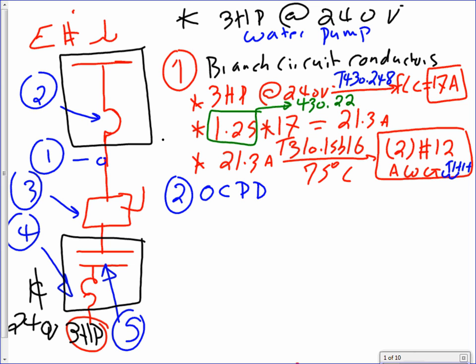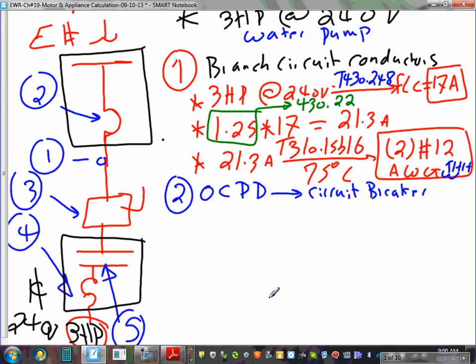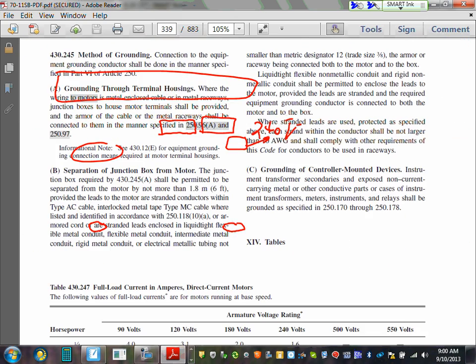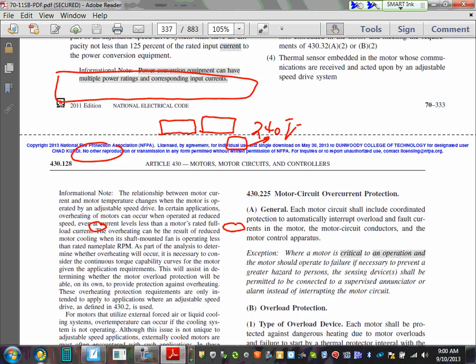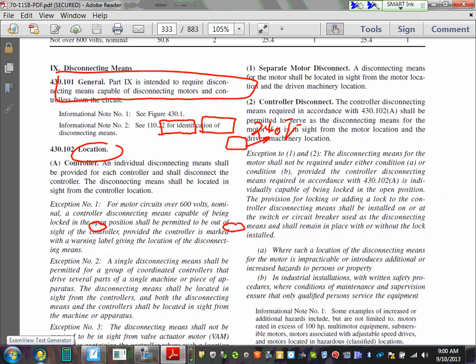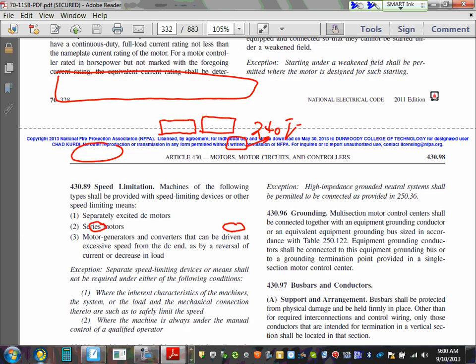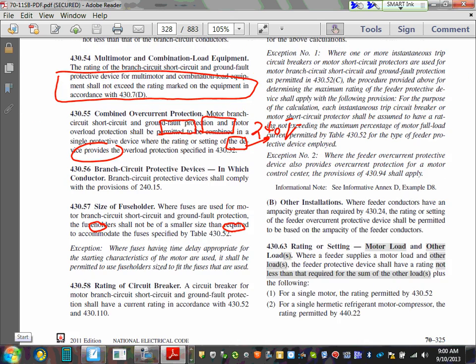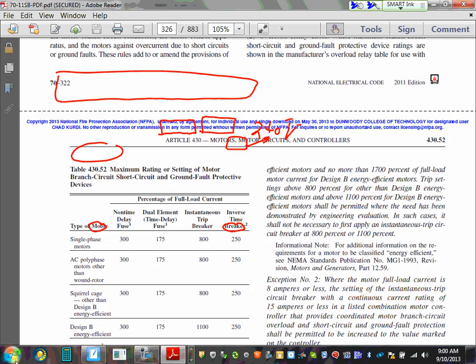For the overcurrent protection device, I need to use a circuit breaker. But for overcurrent protection devices, guys, there are options. You can use circuit breakers, or you can use fuses. So I'm going to go directly to the NEC code book and go to the table that I would like you guys to highlight: 430.52. Come on, 430.52. Right, there you go.